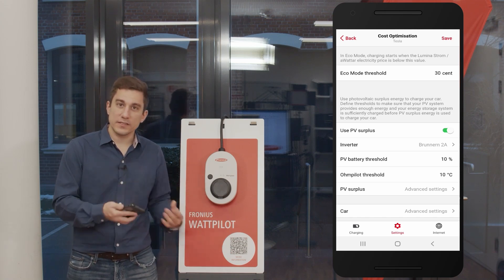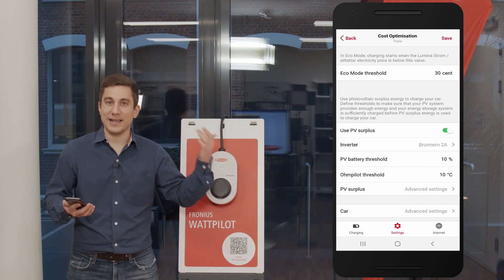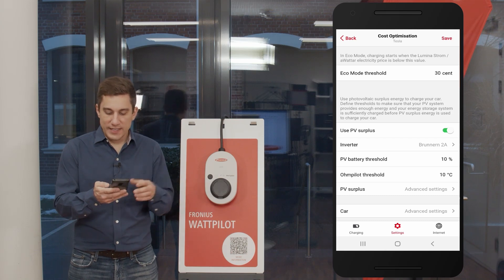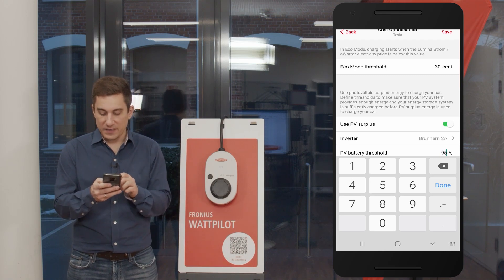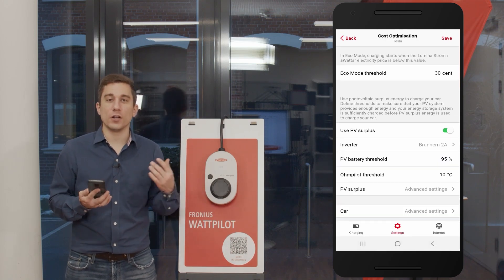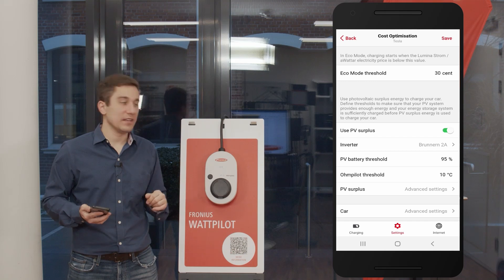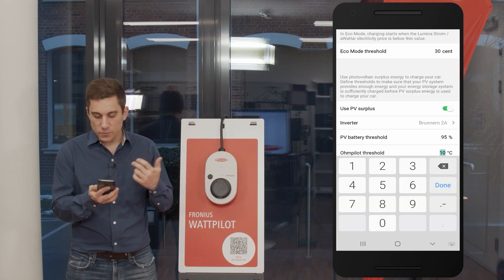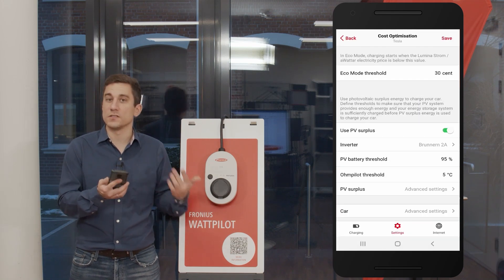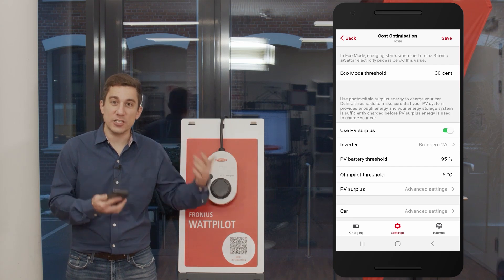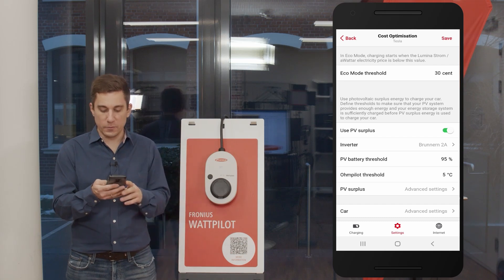That was the first example with Wattpilot at prioritization number one. In the second example, we want to prioritize the stationary PV battery system. We give the PV battery a relatively high value — for example 95% state of charge — to ensure the inverter first charges the battery storage to a very high level before giving energy to the Wattpilot. The Ohmpilot is left at a low value, such as 5 degrees Celsius, so it is easily met, meaning the PV battery charges first, then the Wattpilot, and any remaining energy goes to the Ohmpilot.